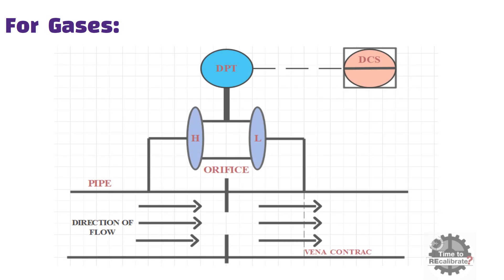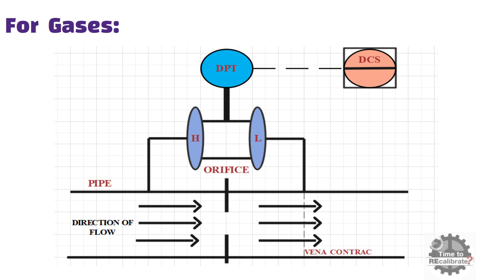As you can see, for gas lines, DP transmitter should be installed above the orifice plate because gases have a property of self-venting. And secondly, gases have condensate formation, so it is better to install above orifice plate.